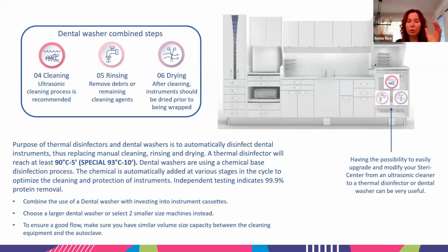Okay, very good. So if you're using an ultrasonic cleaner, of course, it's going to take a little bit more time. You're going to get instruments clean, but it's like a 20-minute cycle time for the ultrasonic. Then you need to rinse manually. And instrument dryers usually run for about 15 minutes. So right there, it's equal in time, but it's a lot less handling. So you don't have to be there at that Stericentre to handle those instruments that are, again, potentially contaminated. So you want to avoid handling those instruments, and that's why dental washers are a big advantage in a clinic setting.